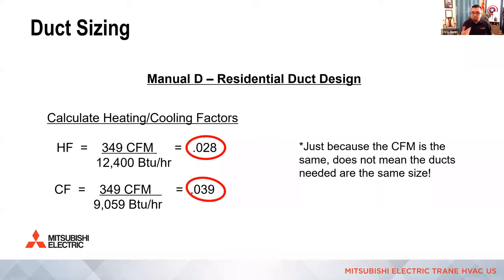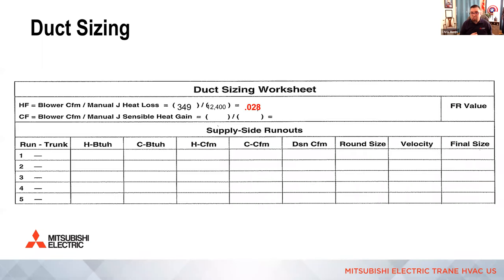All right, so those are the two numbers we're going to transfer over to the duct sizing worksheet. And in this example, because we're not in person and I can't have you do this with me helping you at each and every step, I just color coded this to make sure you see where the math goes. So heating is going to be in red, cooling is going to be in blue, and then of course your design numbers are going to be in green. Okay, so you can see we transferred over the 0.028 in heating, the 0.039 for cooling factor. And then of course the calculated friction rate we came up with on the other page of 0.08. That's what we're going to set our duct calculator for to size the runs.